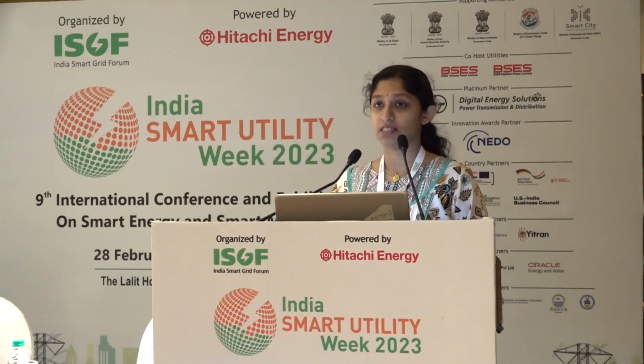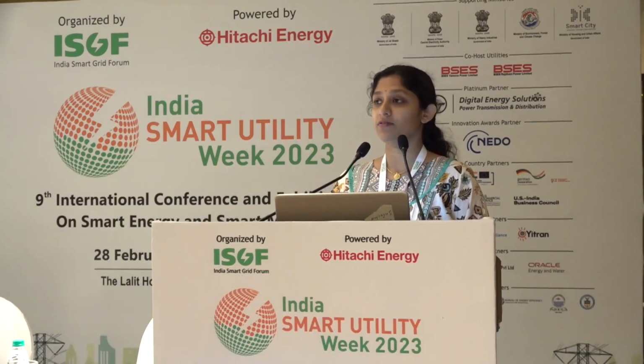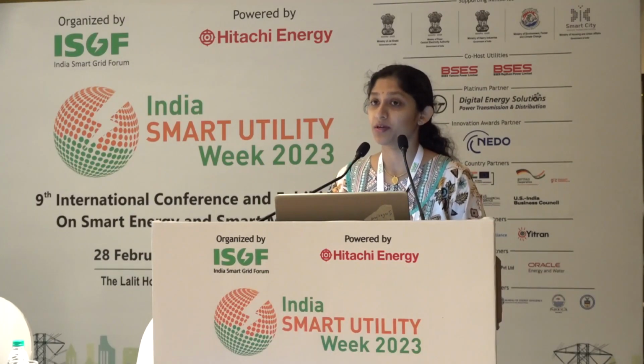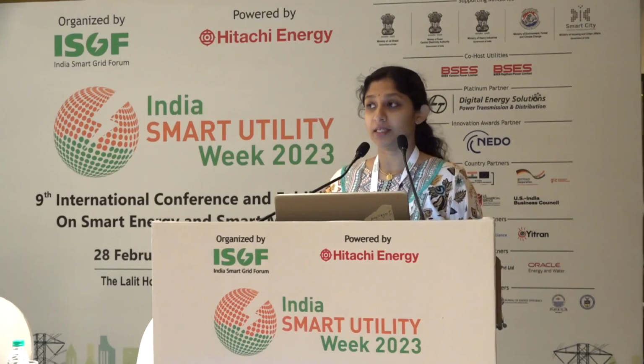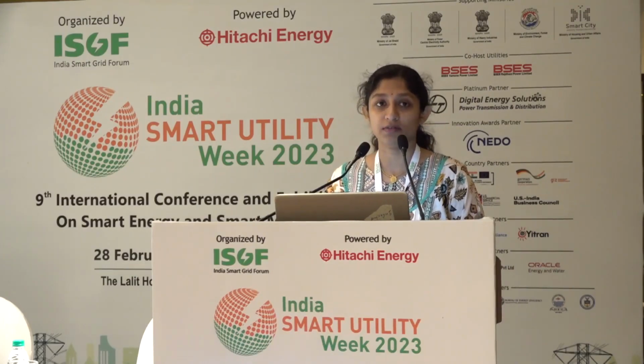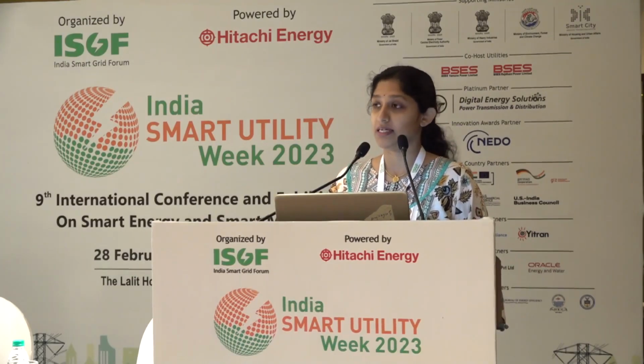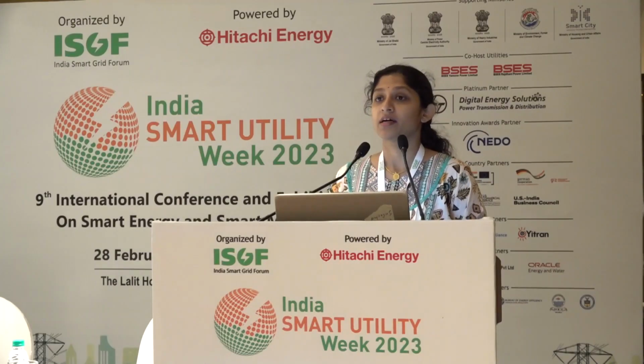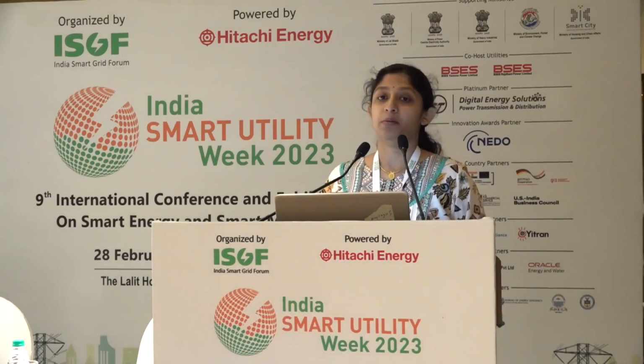Why this is relevant here is because unlike any other system, in a substation, especially a digital substation, at the level of goose packets and sample values, you have unencrypted messages flowing in the network, and because of the multicast protocol used, you also have unacknowledged messages.